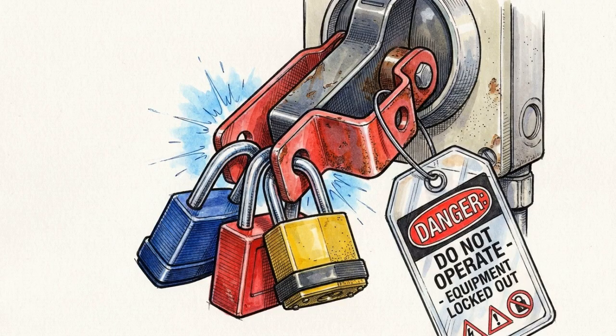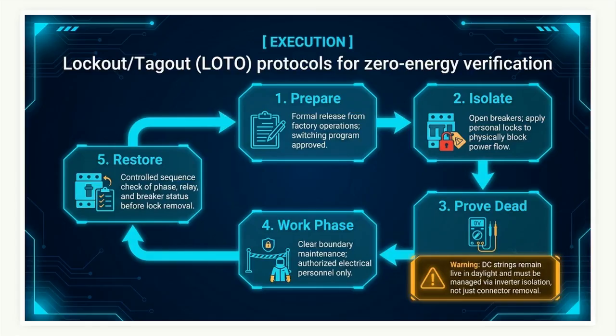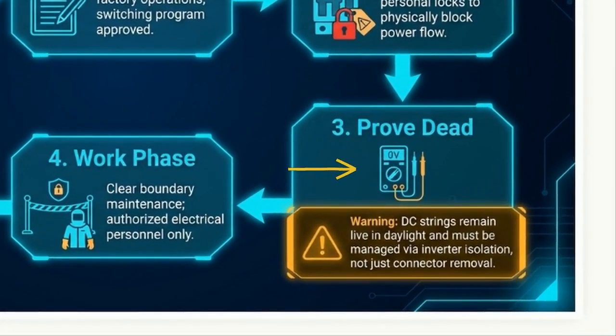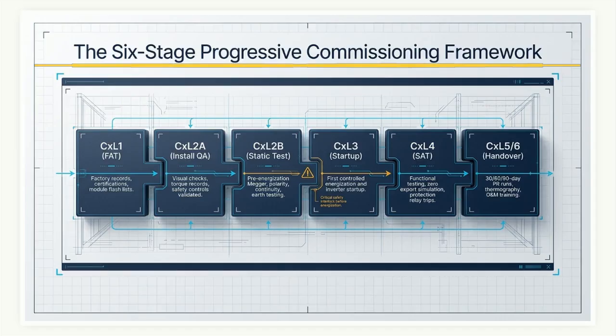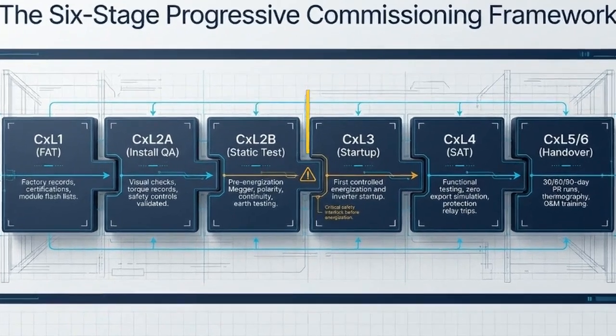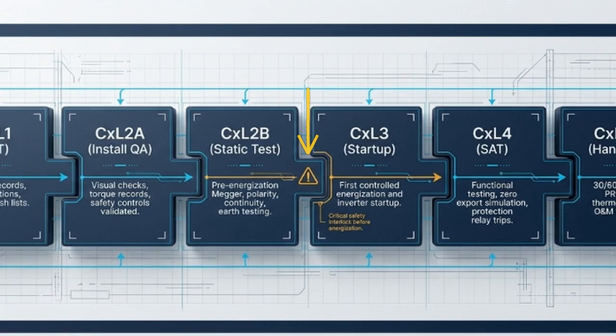This flowchart outlines the strict 5-step lockout and tagout protocol used to isolate the substation. The process explicitly accounts for live DC strings. Step 3, prove dead, requires a physical meter test. No worker touches the bus bars until zero energy is verified. Once construction is safe and complete, the project shifts into a rigorous 6-stage progressive commissioning pipeline, systematically verifying every component before the plant is brought to life.